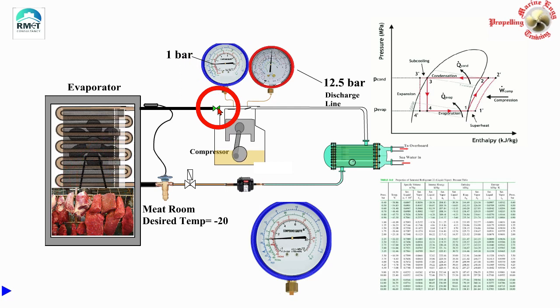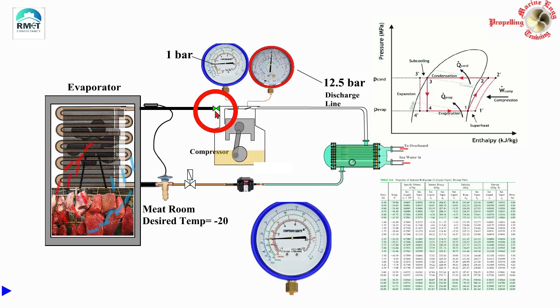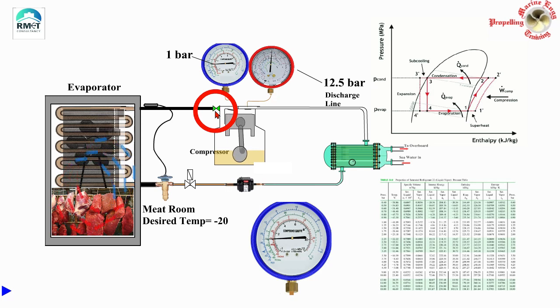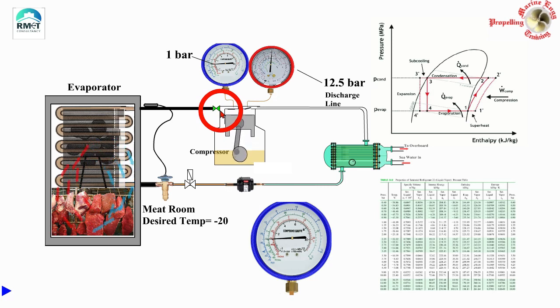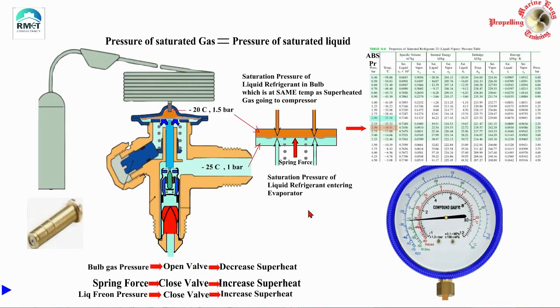We also learned how to get critical information from the suction and discharge gauges, and we discussed the phenomenon of frosting on the suction pipe. With a good understanding of condensation and dew point, we understood that frosting or icing on the pipe nearest to the compressor suction does not necessarily mean liquid is returning. However, to be clear: if liquid is returning — which is undesirable — the likelihood of frosting is very high provided certain conditions are satisfied. In this video we will also discuss the myths associated with liquid return and why liquid should not return to the compressor.